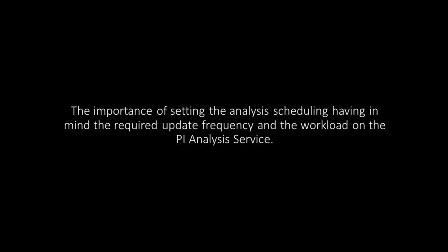The second issue we had a look at was the importance of analysis scheduling. Now, this often relies on just a lot of common sense. If you are only going to be looking at a report once a week, there's probably not a need to run that calculation every minute. If it's a summary calculation, you could maybe run it once a day at midnight when the load on the system is low. You can also have a look at periodic event-triggered scheduling for your analyses. And that's fantastic when you need to trigger based on a specific value updating. So scheduling your analysis, the standard 1 minute or 5-second trigger is often not the best decision to go with.